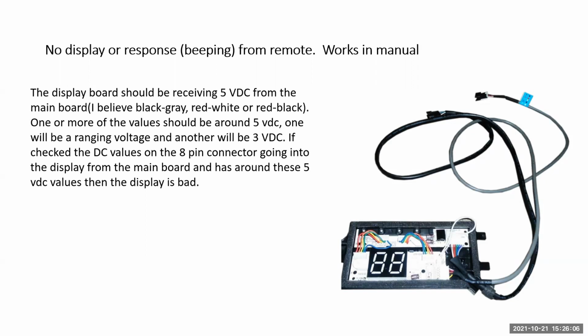One might be ranging and another might be around 3 volts. That's nothing really to panic about. We are getting voltage there and it's talking. You can try this in the manual mode and see how the unit reacts. You can also shut the blower off and on. You want to make sure the remote is pointed at the IR receiver.